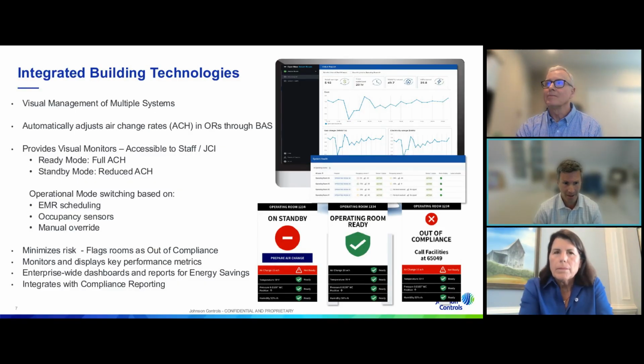A lot of them will say, listen, we know the operating room is consuming a lot of energy. We know why. It's because of these ASHRAE 170 standards, running to these high airflow, high HVAC requirements. And we know we can set it back, but we don't, because the capabilities available to me in my HVAC control system just don't account for the complexity that exists within an operating room. As Charlie mentioned, when you need the operating room for surgery, whether it's a planned surgery in the middle of the day or an emergency surgery in the middle of the night, or maybe just a surgery that goes over, how do you account for all that and make sure that the operating room is in the right parameters if you are taking a setback strategy?